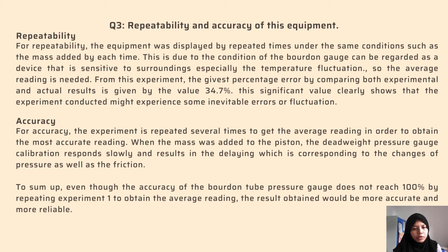In terms of accuracy, the experiment is repeated several times to get the average reading in order to obtain the most accurate reading. When the mass was added to the piston, the dead weight pressure gauge calibrator responded slowly, resulting in a delay corresponding to the changes of pressure as well as the friction. So to sum up, even though the accuracy of the Bourdon tube pressure gauge does not reach 100%, by repeating the experiment to obtain the average reading, the result obtained will be more accurate and more reliable.